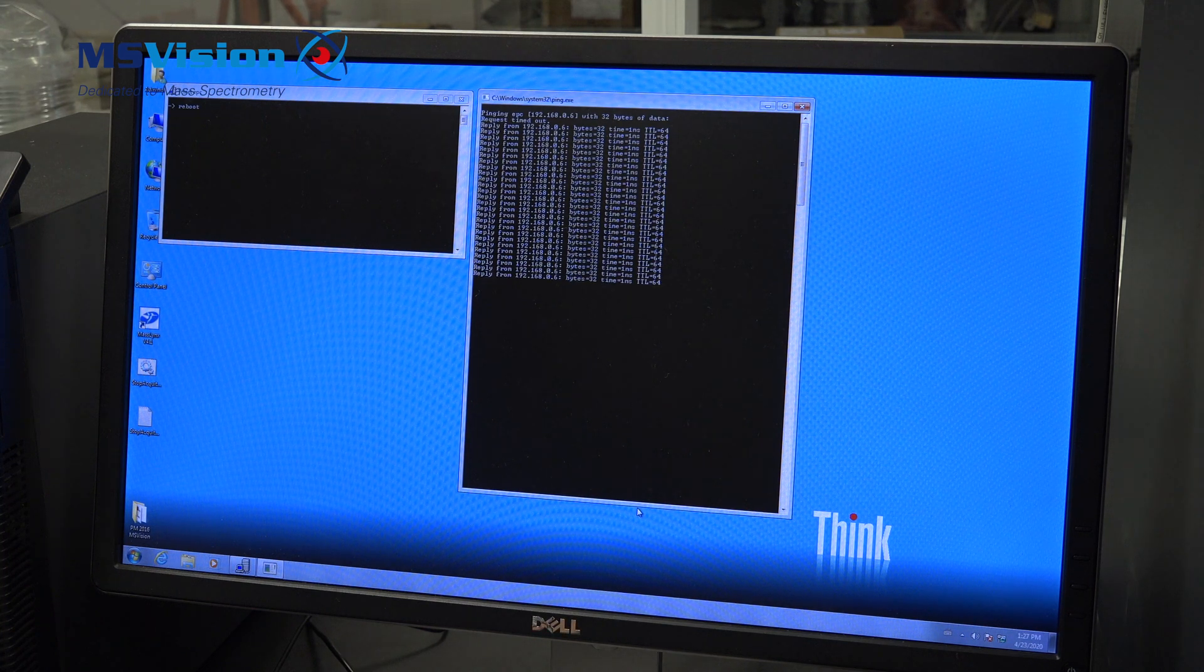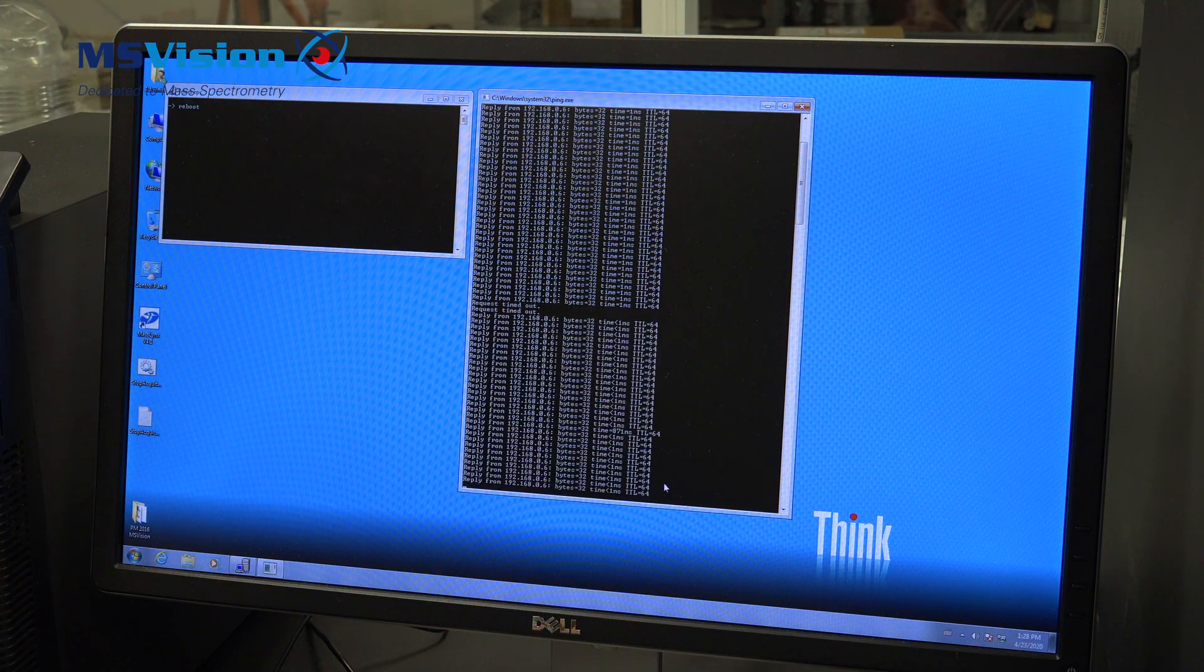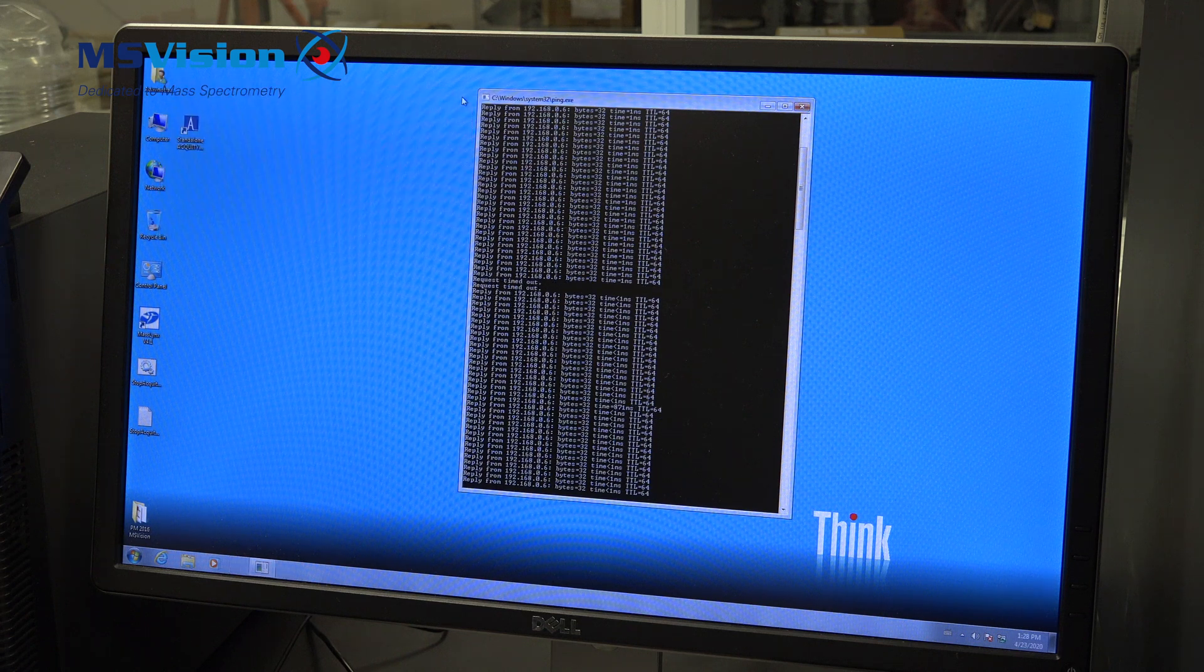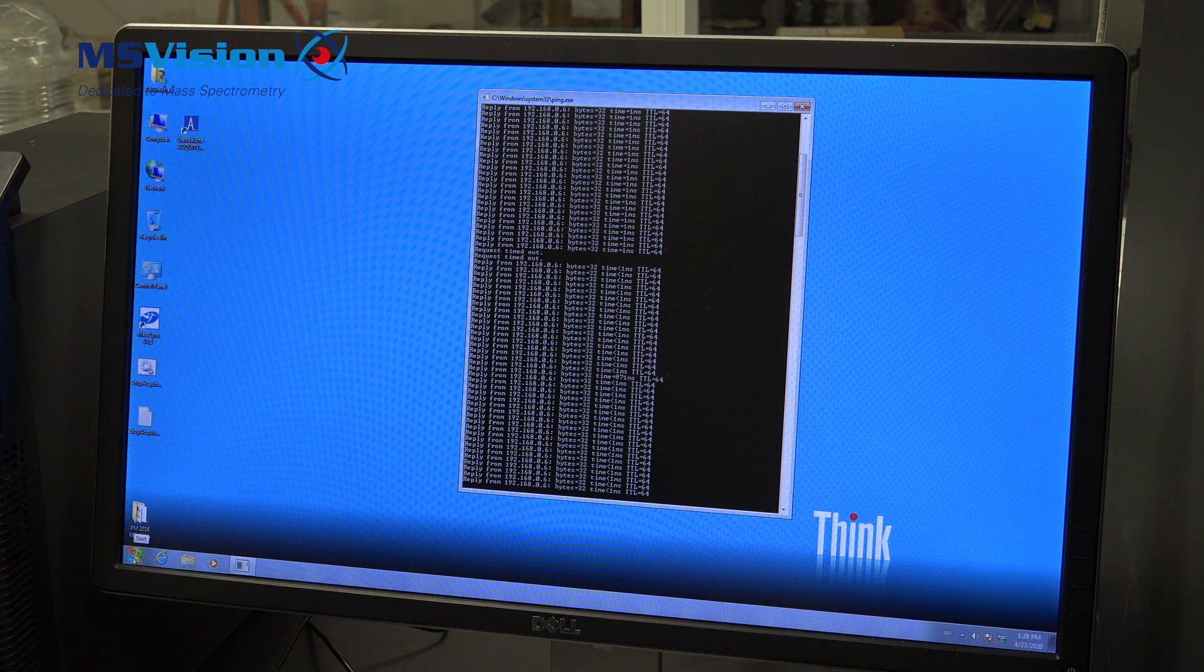Final request time out. This is an internal software booting. When finished, we can close the window. Most likely you can hear the instruments switching a few valves or turning off gas. If the lab noise is quiet enough, you can hear a beep that indicates that the EPC has been rebooted again. We can open telnet EPC, and if the blinking cursor with the arrow is there, it should be communicating.